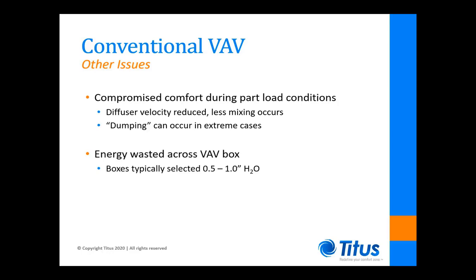VAV boxes also consume fan energy. Most VAV systems are designed with around half to an inch of static pressure upstream of the VAV box. The electrical fan energy used to produce this system pressure is wasted due to the pressure drop across the VAV box.